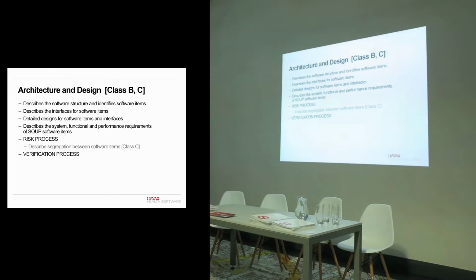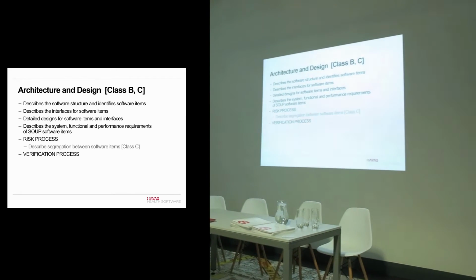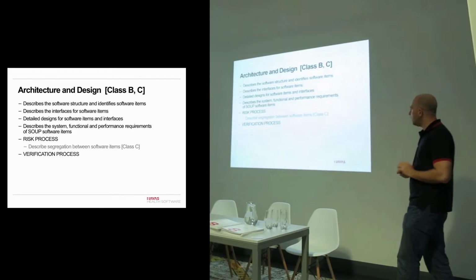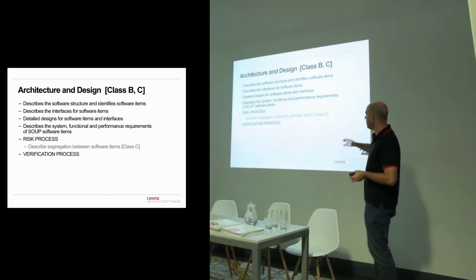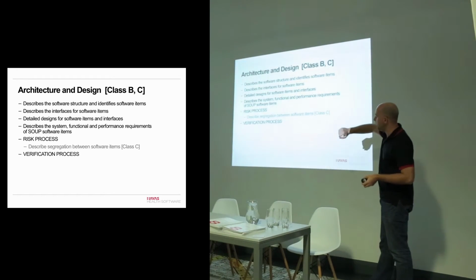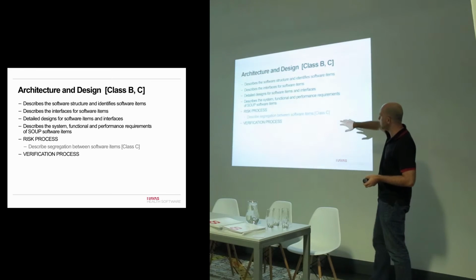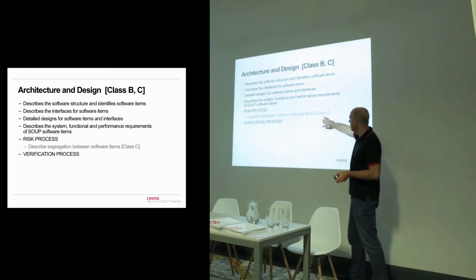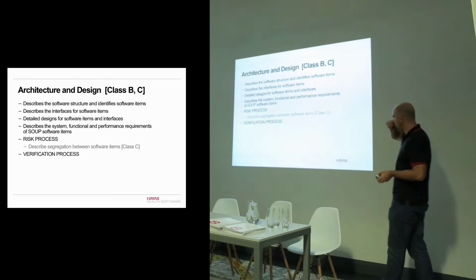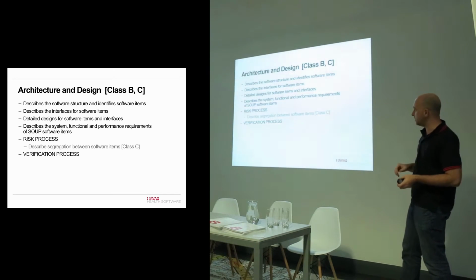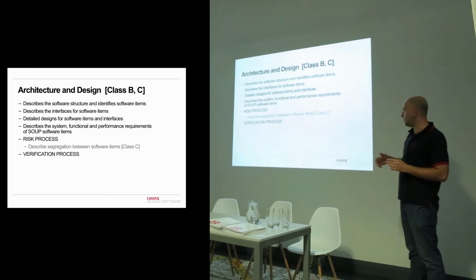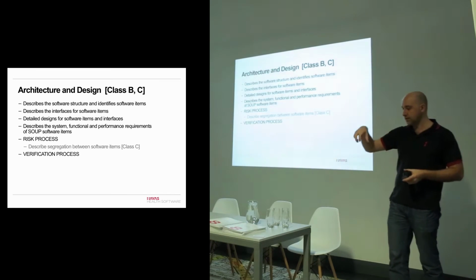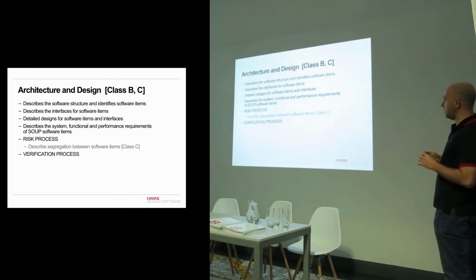You do need to have quite detailed designs as well. There's quite a lot of big design up front, it feels like that, but it's not quite the same. The other thing to bear in mind is that you need a risk process and a verification process, and there's documentation. But for a Class C, this is for Bs and Cs, if yours is a Class C, very high risk, you need to describe what the segmentation is between all the software items, so what the individual risks are, and when you separate those things, what the risks are.